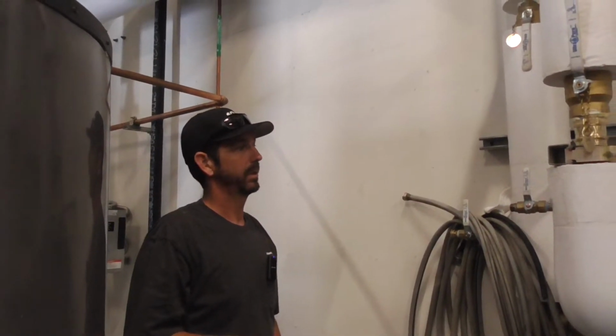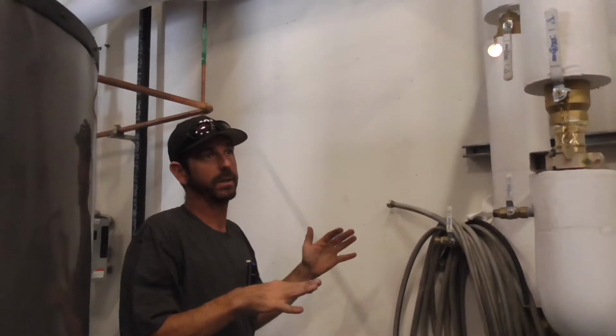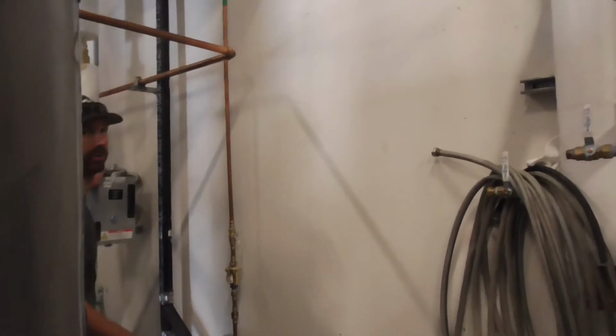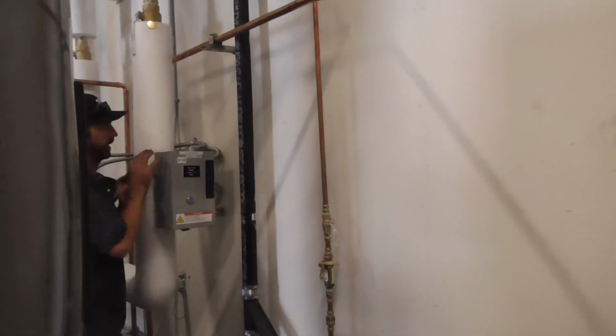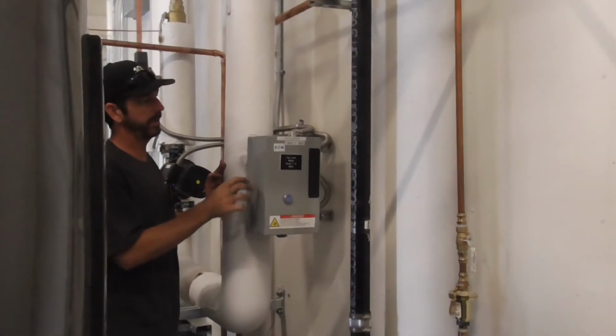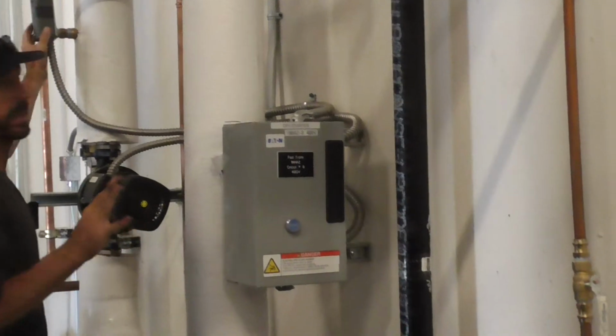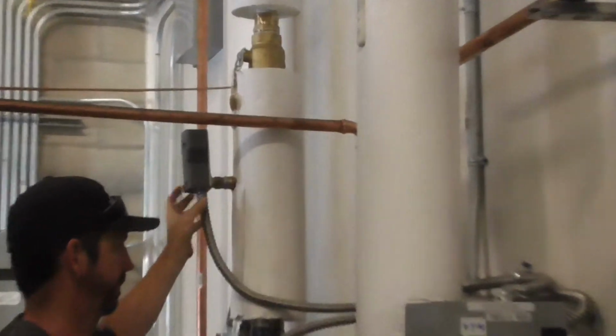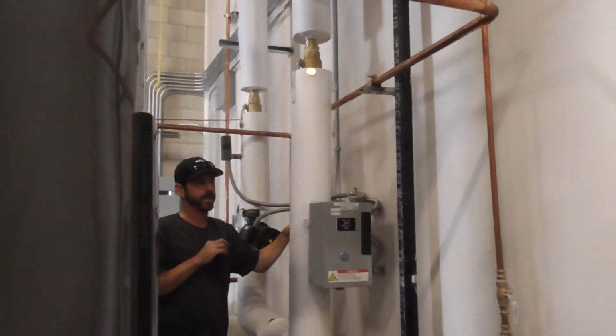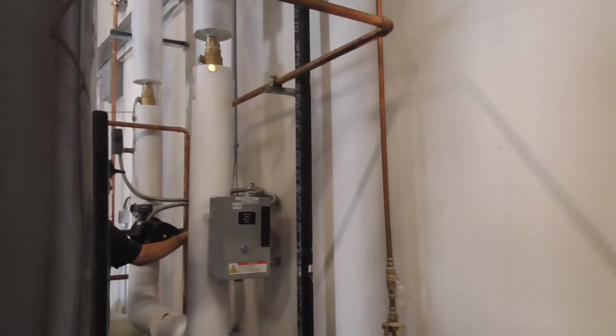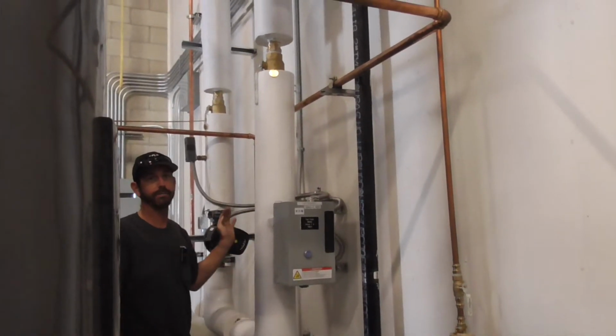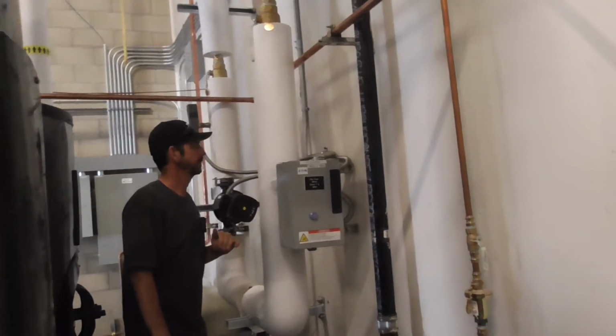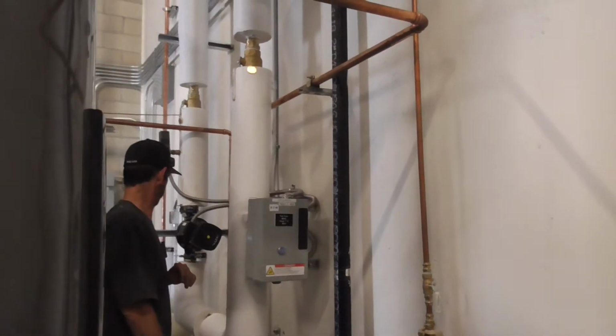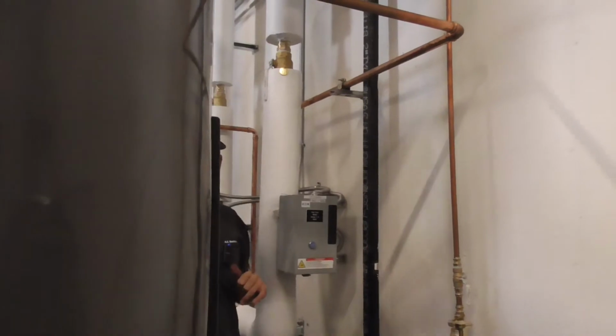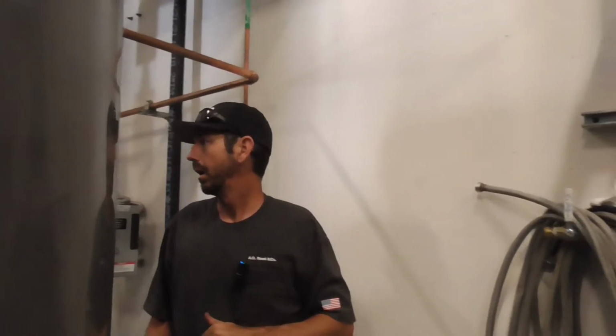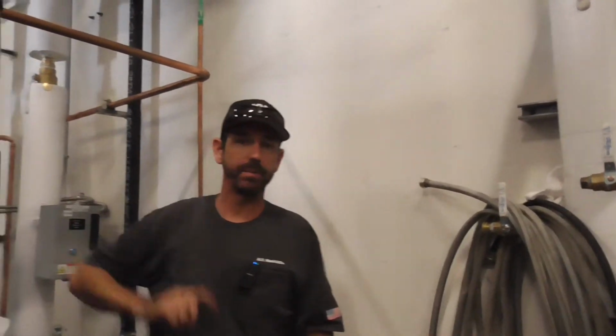Okay. Any other questions on the domestic in here? The domestic is controlled. This is your starter for the domestic. So there's a contactor, overload, and a transformer that runs up to the aquastat right here. Okay. Local switch right here for the starter. Okay. This is 480. It's a 480 volt unit. Okay. The last thing we have in here is the booster pump skid.